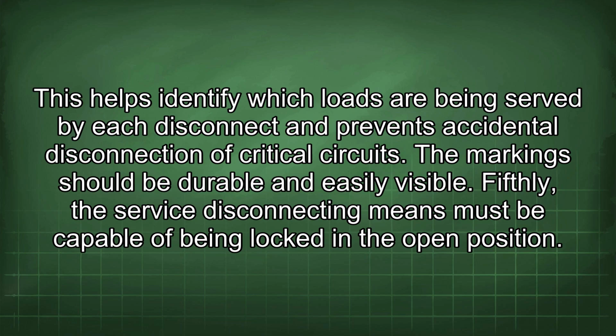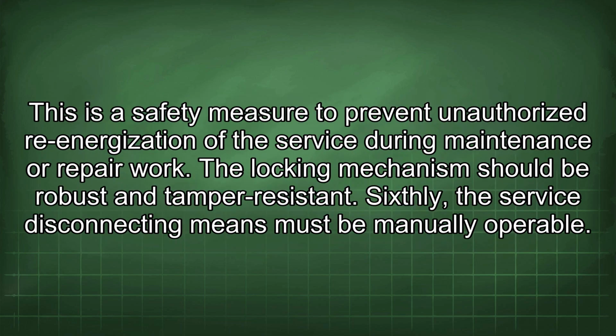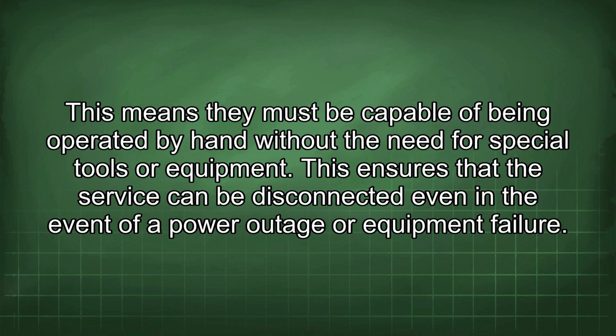Fifthly, the service disconnecting means must be capable of being locked in the open position. This is a safety measure to prevent unauthorized re-energization of the service during maintenance or repair work. The locking mechanism should be robust and tamper-resistant. Sixthly, the service disconnecting means must be manually operable. This means they must be capable of being operated by hand without the need for special tools or equipment. This ensures that the service can be disconnected even in the event of a power outage or equipment failure.